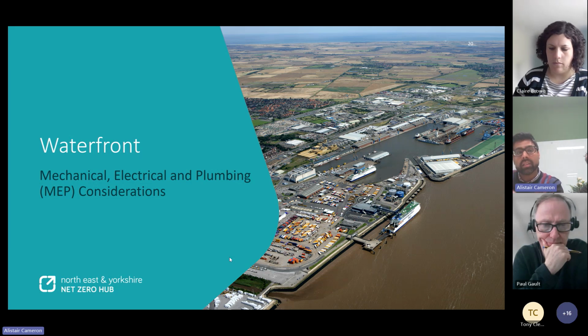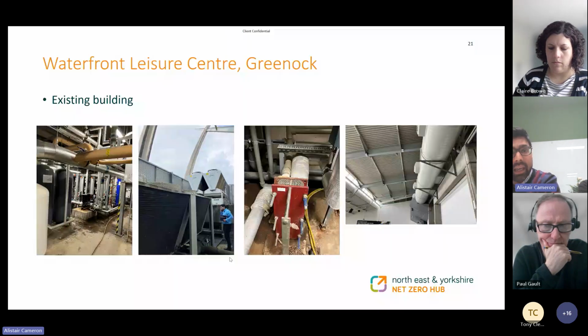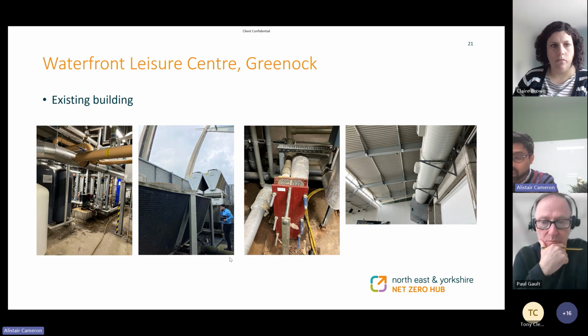But when we look at the waterfront in isolation, and some of the figures that I've presented earlier in the presentation, the existing building itself is obviously a high energy consumer. The building has some quite extreme temperature profiles throughout its footprint. So Alistair talked about the relationship between the ice rink and the swimming pool. And I think that's incredibly important because essentially we have an ice rink where we're conditioning air at 12 degrees in order to maintain the ice on the floor. But then some of the adjacent spaces are heated to 31 degrees where we've got swimming pools and leisure pools.